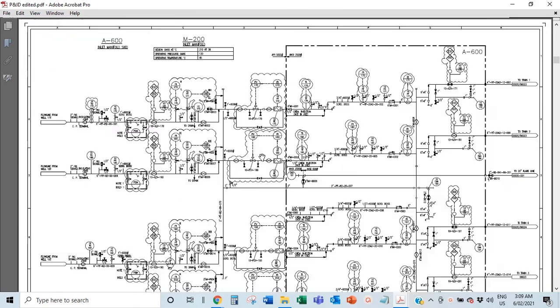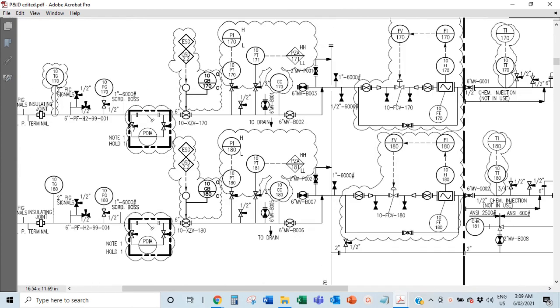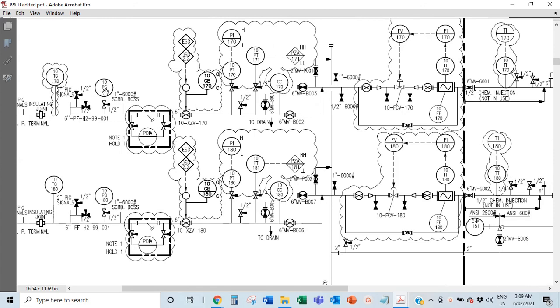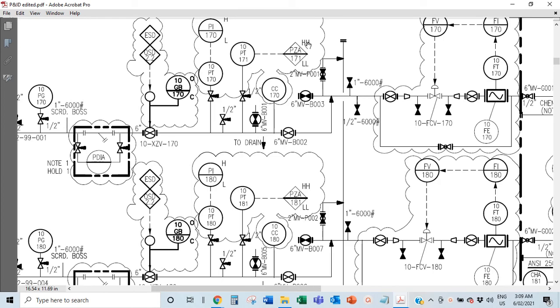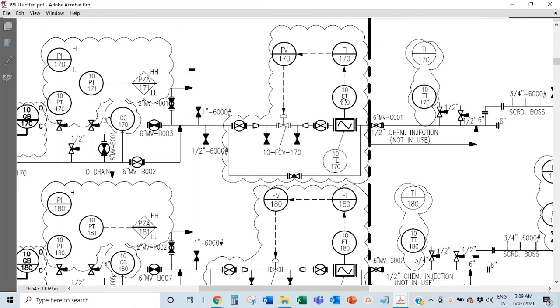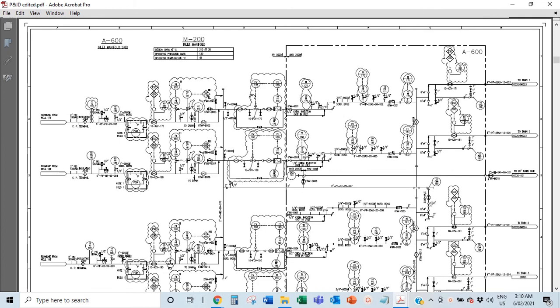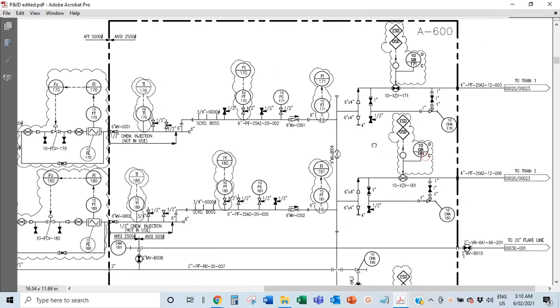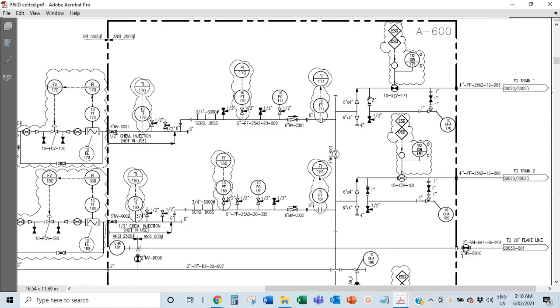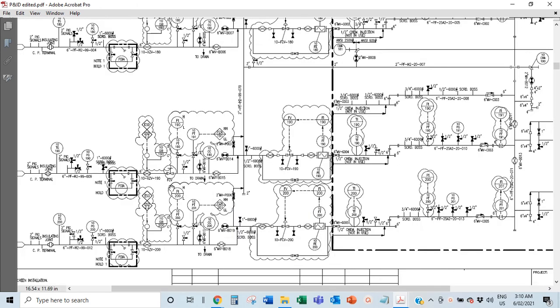Once you understand the legend, all those instrumentation items — high-high, low-low, pressure transmitter, temperature — start making sense. You see PI (pressure indicator), PDI (pressure differential indicator), PIT (pressure indicator transmitter), level indicator, level switch low, level switch high. When you look at the P&ID and see a pressure gauge on a line, you know: we need to know the pressure here. A flow transmitter means we need to know the flow. An emergency shutdown valve means something may happen and we need to shut down quickly. A blacked-out valve means that line is not flowing.